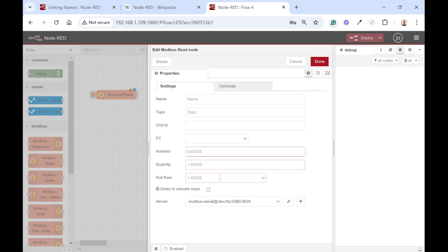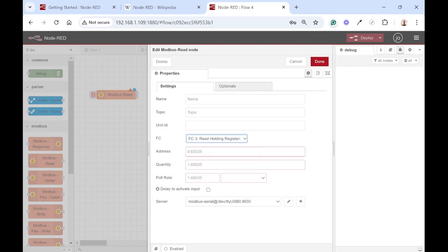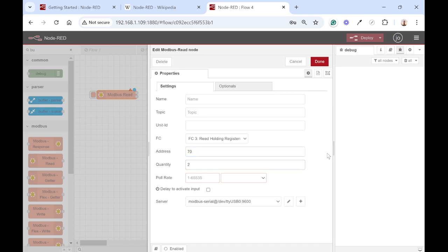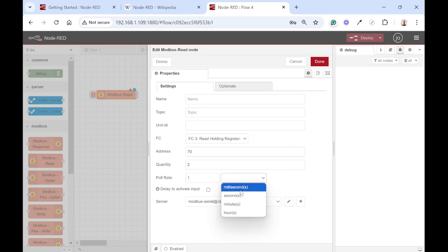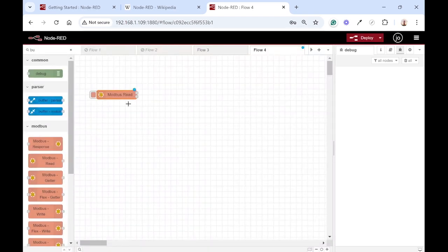The next step is to specify the function code. Firstly we want to read holding registers, very similar to OpenModscan. The address we want to read is 70. This time there is no offset so you enter the address you want to read, not 71. We want to read two registers and let's read it every minute.